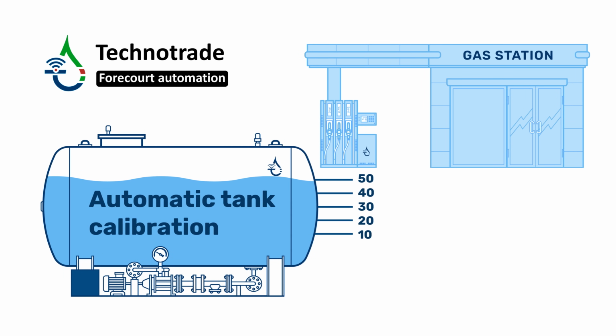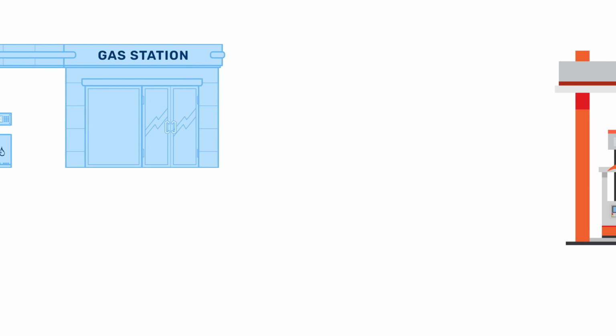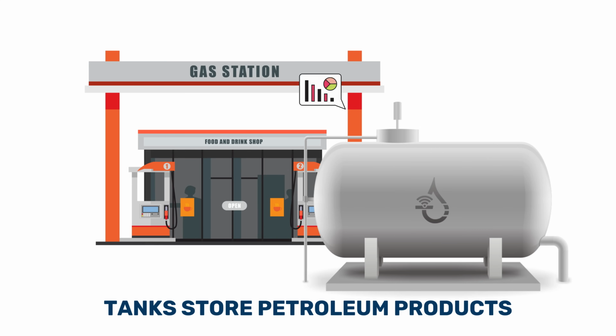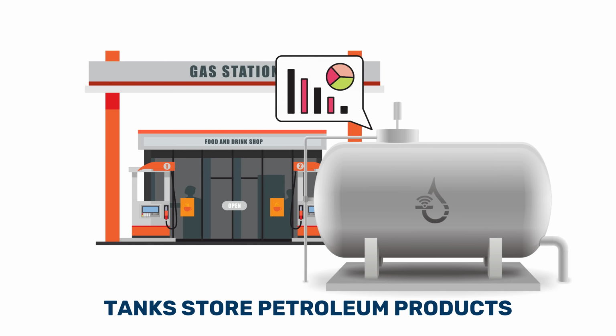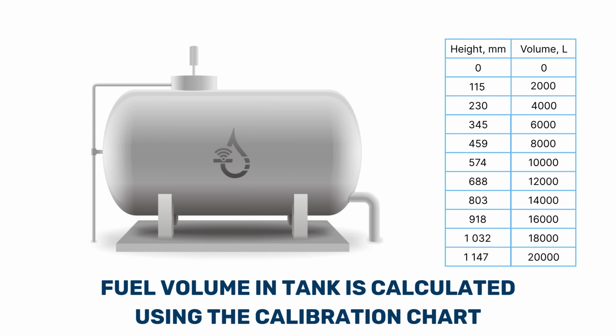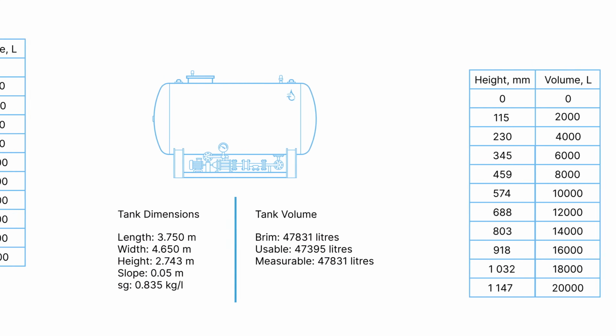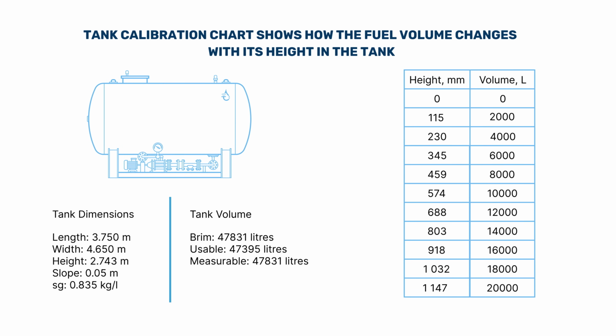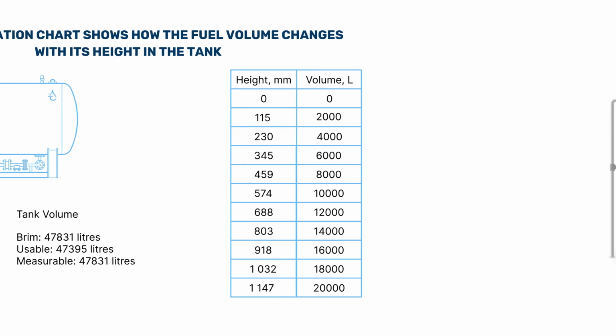Automatic tank calibration. At petrol stations, horizontal cylindrical steel tanks are used to store petroleum products. The tank is a measuring instrument that has a calibration table compiled during its manufacture process. The calibration chart is a document which stores correspondence between the fuel height in the tank and its volume. The tank calibration chart is used for calculation of the fuel volume remaining in tanks, in tank deliveries registration, temperature compensated volume calculation, and so on.